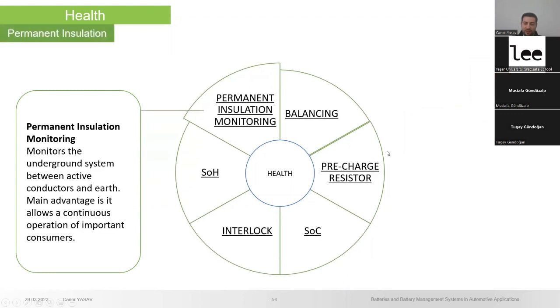There's also another safety component called insulation monitoring. It's a ground system between active conductors and the earth. You need to connect it to earth for the battery management system for more safety, and it has the advantage of allowing continuous operation of important consumers.